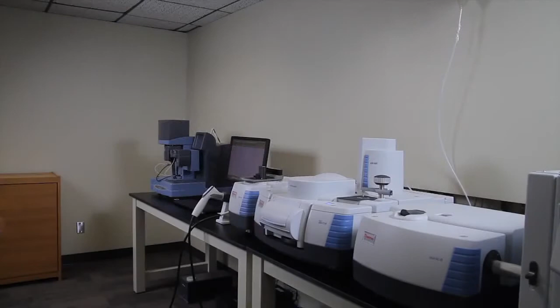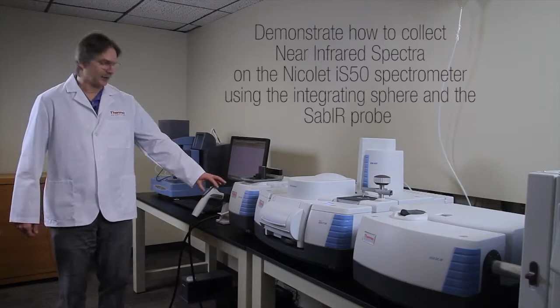Our goals today are to collect near-infrared spectra using the iS50 integrating sphere and collect near-infrared spectra using the SABIR probe that we have attached to the instrument. The labs that would use this particular instrument are QC/QA labs who are looking at incoming materials, also manufacturers who might want to control their processes, and production facilities that would be building methods, chemometric methods, to do their analysis.